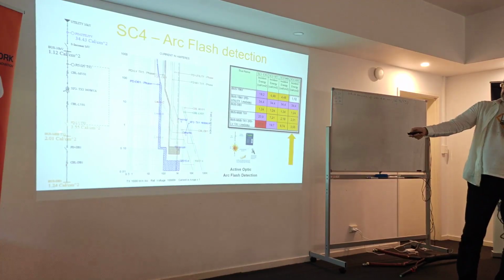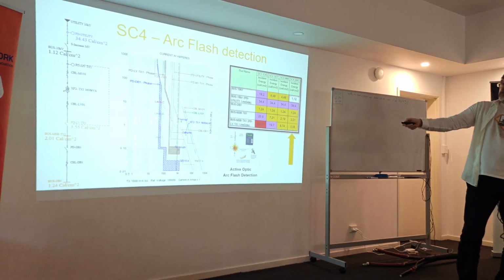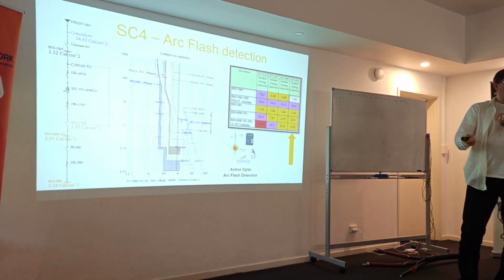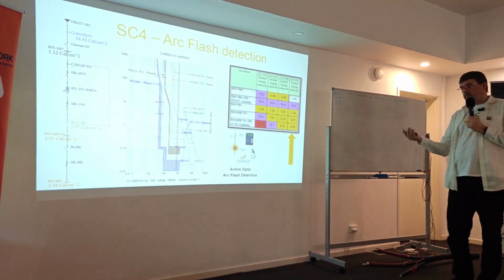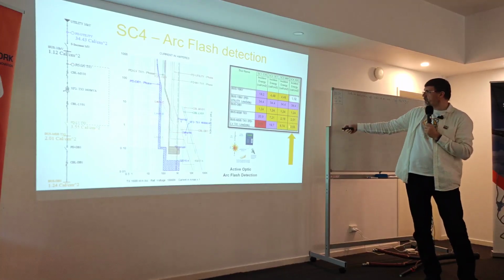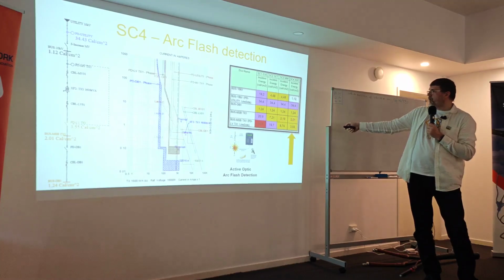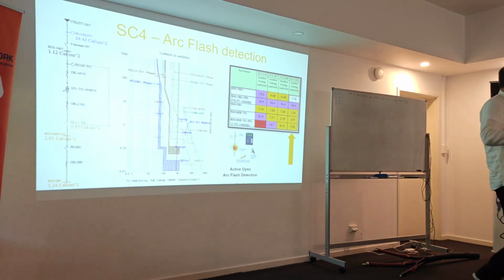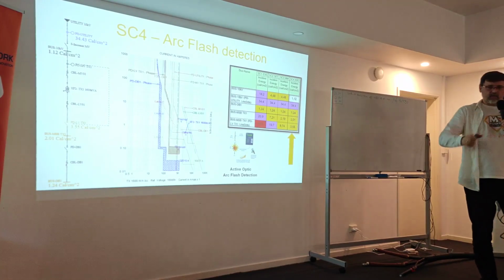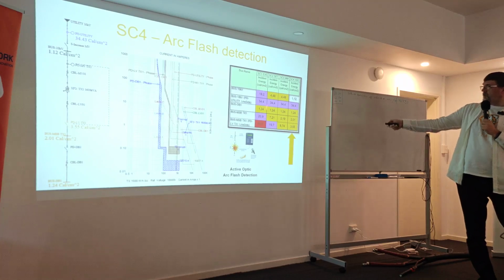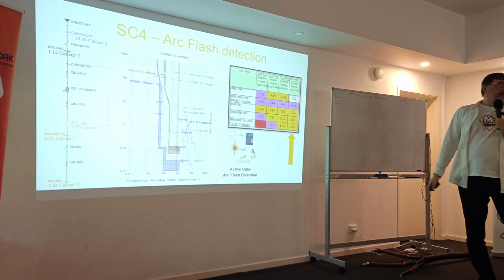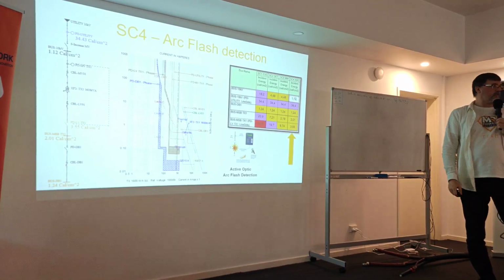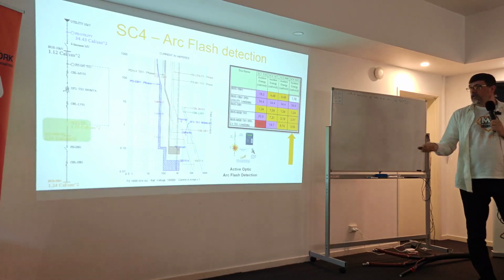So what it does when you install it, and this is an important thing, if you install it in a panel, normally to protect this area, this breaker side, we need to trip one level above, which for us means the medium voltage relay. Not always possible, but technically that's what we are supposed to do. In this case I did this. So the big difference is that we drop from 8 to 3.5. There is no big difference between, for example, this one and this one, yeah? Because the maintenance mode was already on the lower level, like the lowest possible level for breaker tripping. So it's a little bit of difference, but not a huge difference. But if you compare from the reference scenario to this, then we go way below 8 calories, actually below even 4 calories, just to play with those solutions.